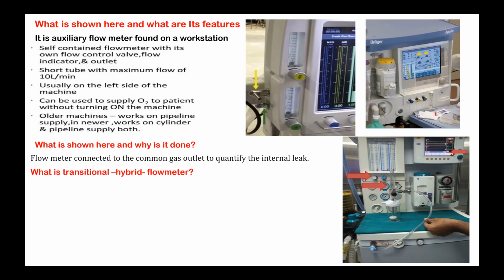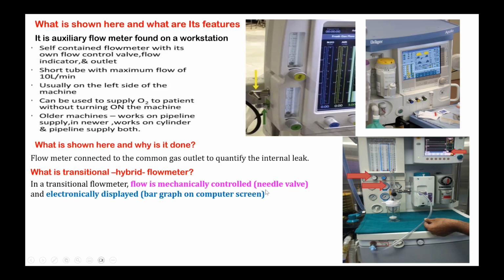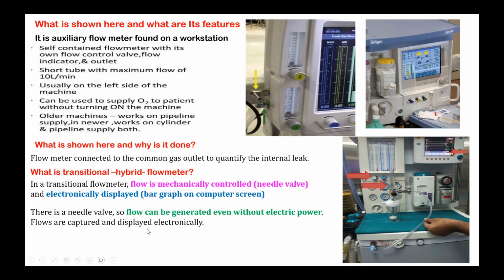So, what is the transitional hybrid flow meter? The newer machines. You can see the flow control knobs are here. But what is the display here? You don't see the glass tube like this. But you can see this on the electronic display. So it is a flow mechanically controlled with electronic display. That is called the transitional hybrid flow meter. And there is a needle valve so that flows can be generated without electric power, and flows are captured and displayed electronically. Electronic flow meters allow automated anesthesia record keepers to chart fresh gas flow. That is the reason why this is being introduced in the world.